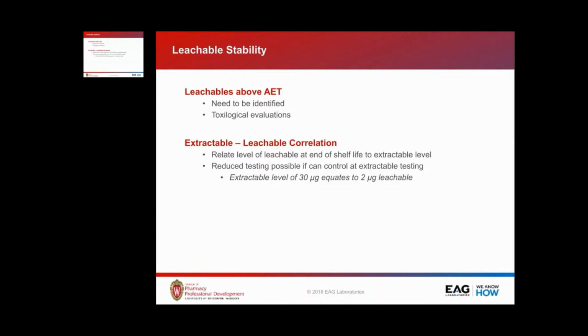With leachables, you're dealing with a wide range of compounds, from elastomeric components to colorants to plasticizers, non-slip agents, and a wide range from very polar, very small molecules to very big polymer fragments. So you can end up with a wide range of toxicity concerns. So it's important to make sure that anything above that AET, you do the proper overall tox evaluation on it.